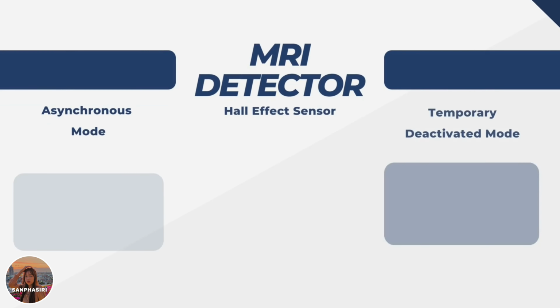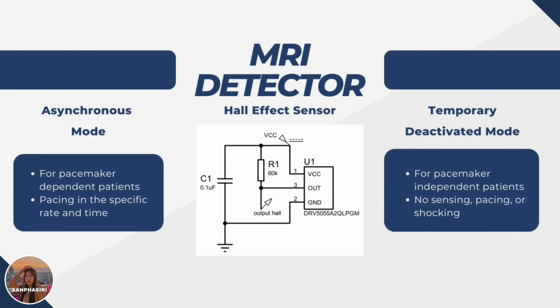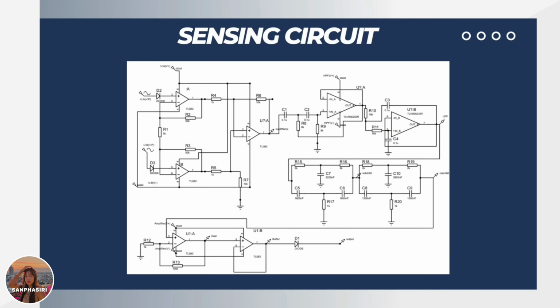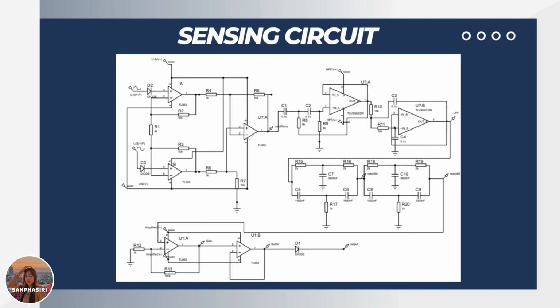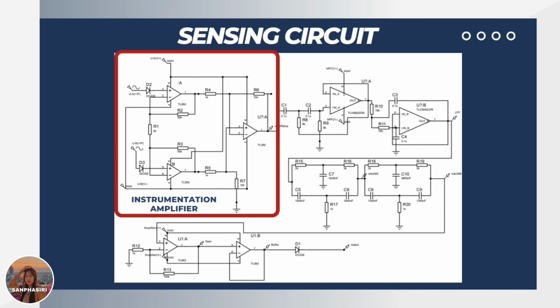The Hall effect sensor is used to detect the magnetic field around the device. If the magnetic field is present, the output voltage will be half of the supply voltage. To connect the Hall sensor to the microcontroller, the datasheet recommended adding a capacitor and resistor in between. The purpose of the sensing circuit is to sense the desired signal. Starting with a differential amplifier as an instrumentation amplifier to receive the difference of two input signals from electrodes as bipolar recording. The result is known as intracardiac electrogram or IEGM.